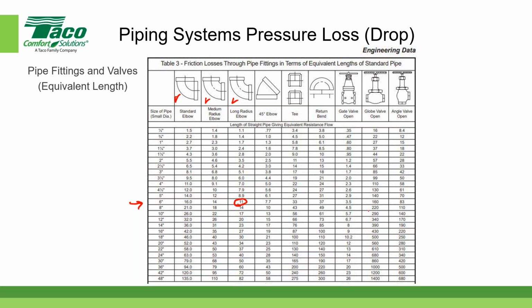Let's just skip down here, for example, to a globe valve. Now, I wouldn't expect you to use a globe valve in an HVAC system designed for normal flow in a piping system. You might use a globe valve for the shutoff of a hose bib or something along that idea. But look at the equivalent length of pipe. It's 160 feet long. That means the pressure drop across the globe valve would be equal to a straight length of pipe of 160 feet. If we look at a gate valve, you'll notice over here the gate valve is only 3.5 feet. The pressure drop across a gate valve is less than the pressure drop across a standard elbow.